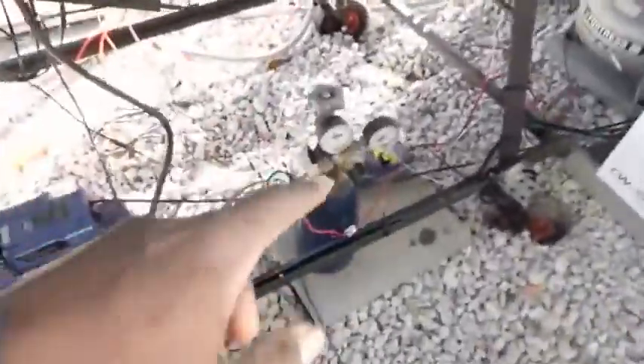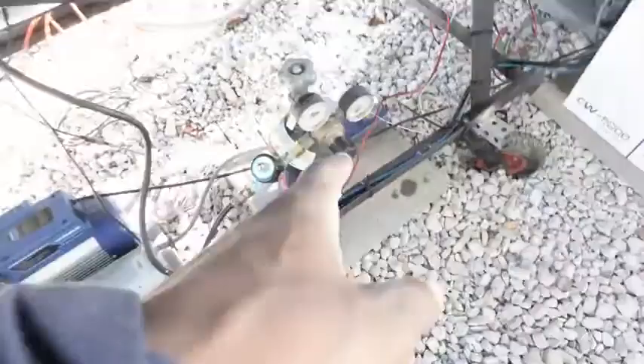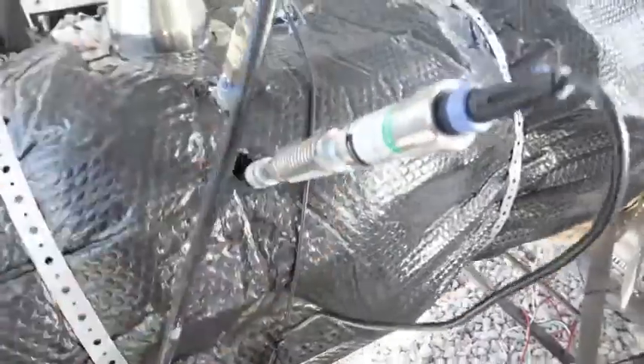Also, argon. I got argon hooked up to a solenoid here - this is the emergency vacuum brake argon. If the vacuum breaks in the machine, and let's say a gasket leaks and air starts to suck in, I need to push this argon in instead to displace the air so it doesn't form a flammable mixture and blow up. So if I see on the computer that my pressure sensor shows the vacuum dropping rapidly, I hit that valve, blast in argon, and we'll be safe.